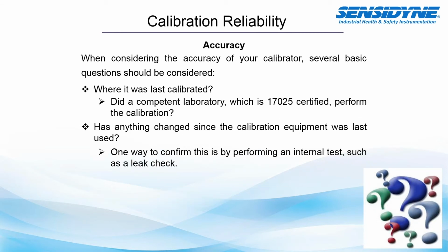Also, when considering the accuracy of your calibrator, you want to know where it was last calibrated. Was it performed at a competent laboratory? Did that laboratory have an ISO 17025 calibration? Also, has anything changed since the calibration was last used? One way you can see if there's excessive abuse on the equipment is to perform a leak check, if such an option exists on your particular calibrator.